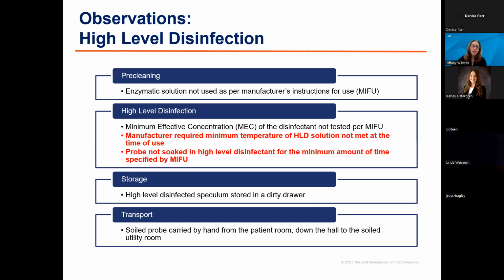Or the item is not soaked in the high-level disinfectant for the minimum amount of time specified by the manufacturer's instructions for use, right? This is the contact time. So if the IFU says 12 minutes and it's only soaked for 6 minutes, the manufacturer of the high-level disinfection solution will not guarantee that the item has been appropriately high-level disinfected.